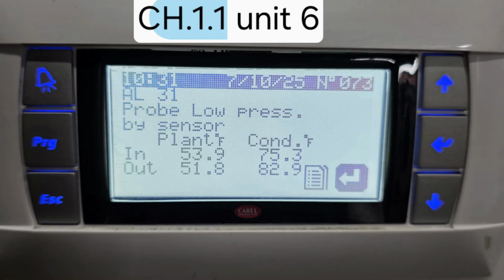A low-pressure alarm means the suction pressure in the evaporator is lower than normal. This usually happens when the system isn't absorbing enough heat from the air or water loop. Common causes include low refrigerant charge due to a leak, dirty or frozen evaporator coil, low water flow through the evaporator, expansion valve stuck closed or restricted, operating in very cold ambient conditions without proper control adjustment.